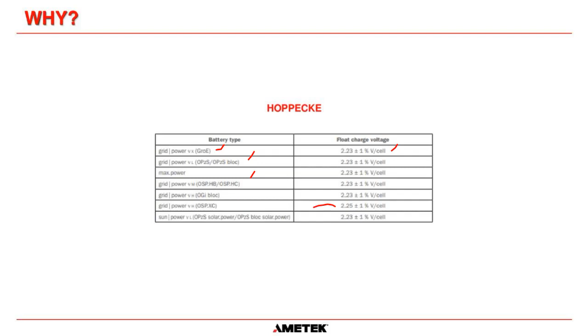Hopefully that makes sense. And I've picked one other manufacturer just to throw it in there. They're actually a lot easier. They're saying, look, here's our type of cell, and here is the float voltage. And in truth, the float voltage is the same for every cell except for this one here. The grid power OSP.XC from Hoppecke is 2.25 volts per cell, and all the others are 2.23 volts per cell.